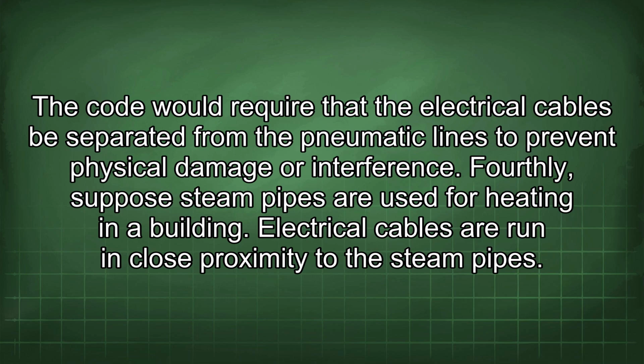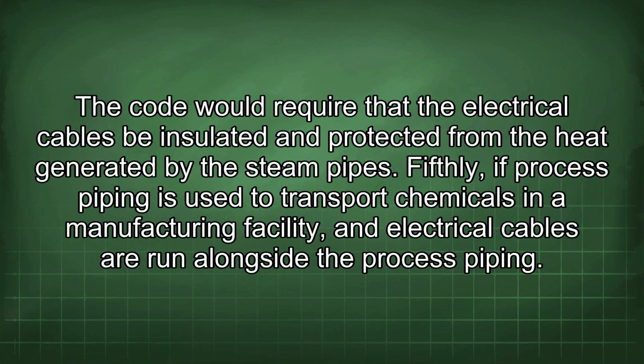Fourthly, suppose steam pipes are used for heating in a building. Electrical cables are run in close proximity to the steam pipes. The code would require that the electrical cables be insulated and protected from the heat generated by the steam pipes.